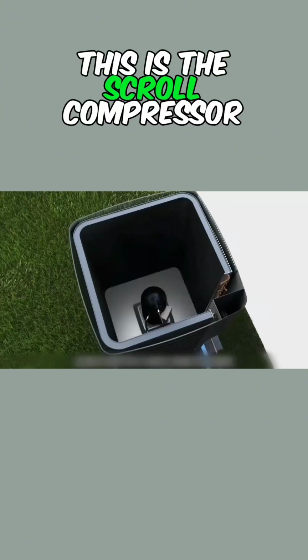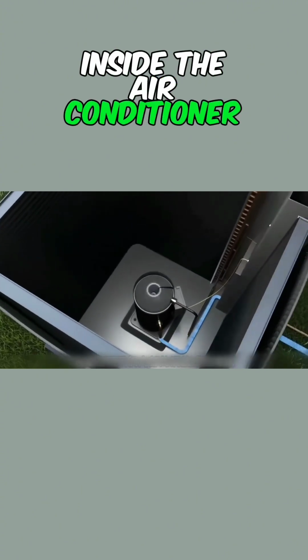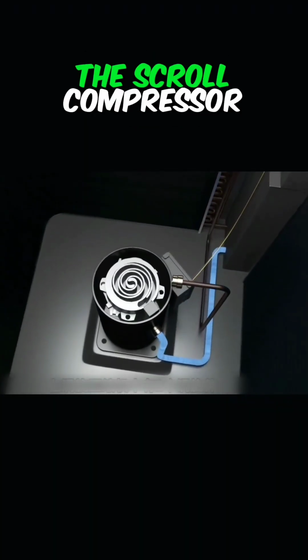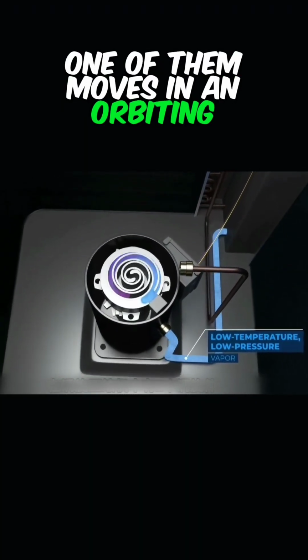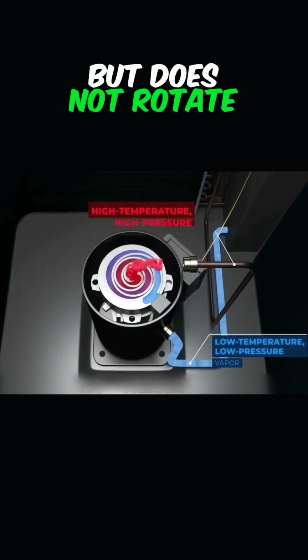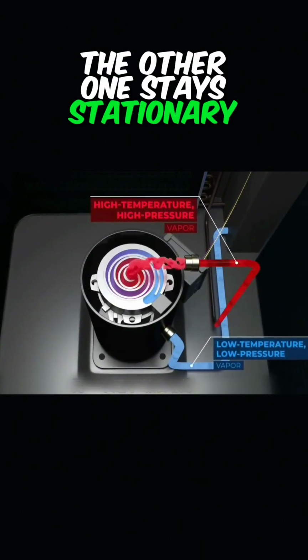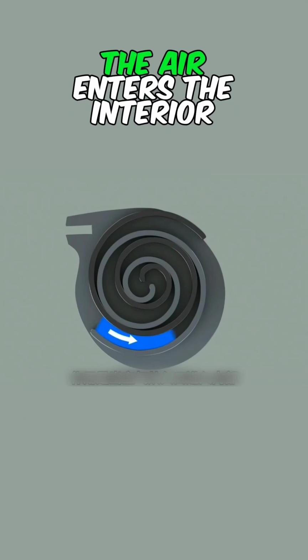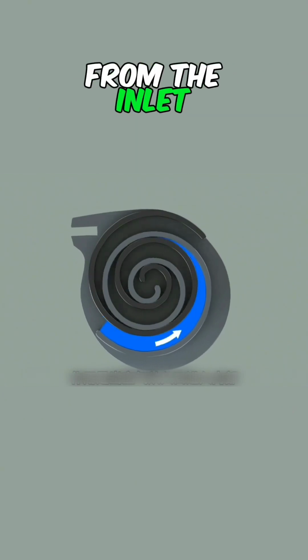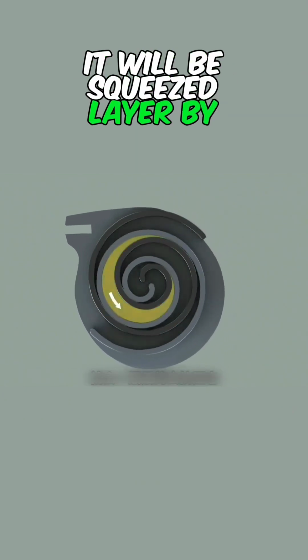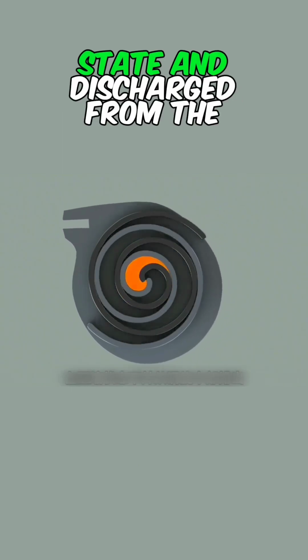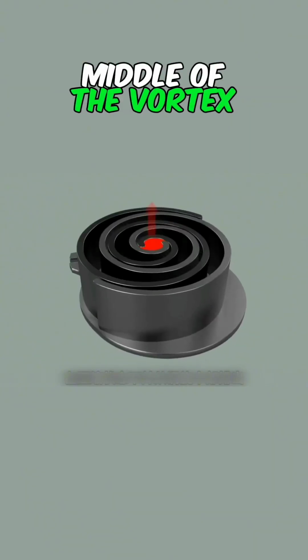This is the scroll compressor inside the air conditioner. There are two main parts in the scroll compressor. One of them moves in an orbiting pattern but does not rotate. The other one stays stationary. The function is that when the air enters the interior from the inlet, it will be squeezed layer by layer in a compressed state and discharged from the middle of the vortex.